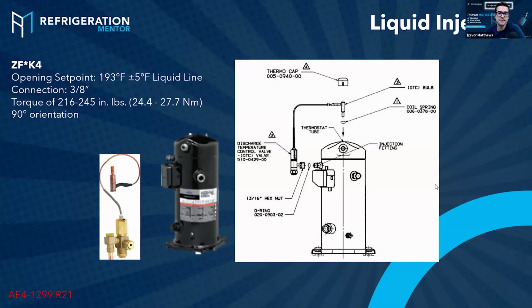Let's see in the chat. There it is, 225 Fahrenheit, around 107 Celsius. Because what's going on inside the compressor is another 50 to 75 degrees Fahrenheit, getting you up to that 300 degrees Fahrenheit, which is bad, which is around 150 Celsius, which is real bad for the oil. The oil starts to lose lubrication, starts to break down, and it leads to a failure. Hopefully that answers your question.